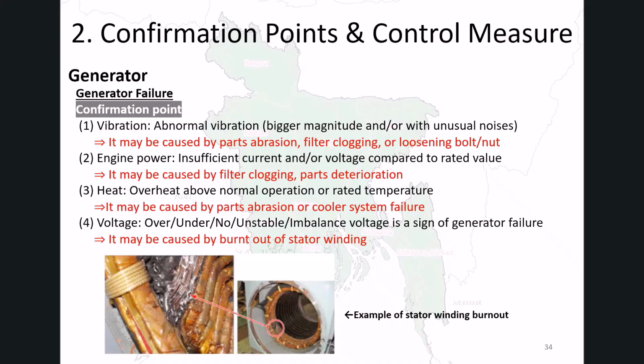First, vibration. If abnormal vibration or unusual noise is observed, it may indicate parts abrasion, filter clogging, or loosened bolts and nuts. Operators should carefully monitor vibration levels and unusual sounds during operation. Ignoring these symptoms may result in severe mechanical damage.